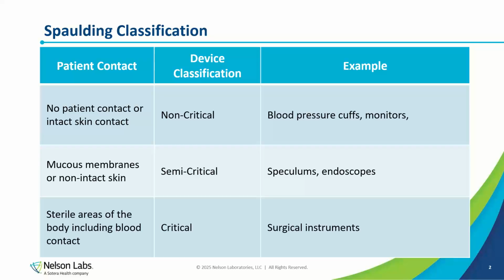So with your critical devices, those are entering the blood pathway and entering parts of the body where you generally don't have large amounts of organism. And so if you're introducing a contaminated device into that part of the body, you are going to give that organism a really good opportunity to spread. Whereas with endoscopes, the mucous membrane contact that they're coming in contact with, there are already microorganisms there. And so whatever microorganism you may introduce is going to have to outcompete the existing organisms there.